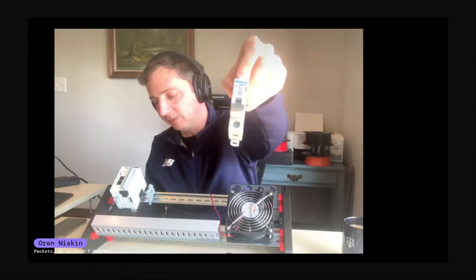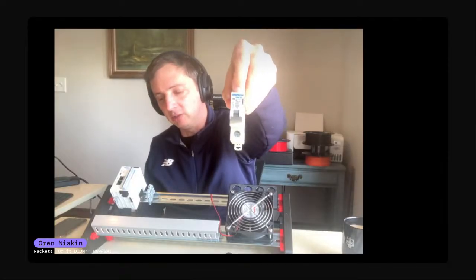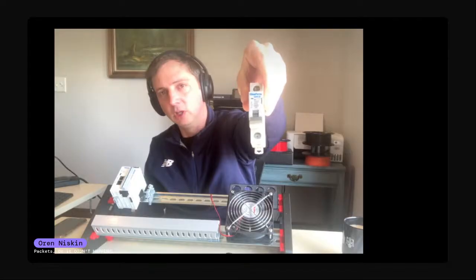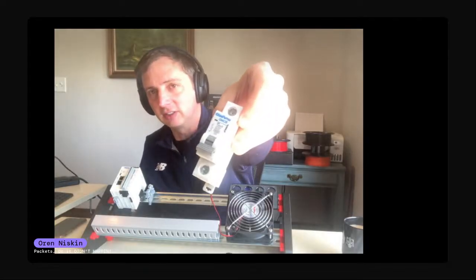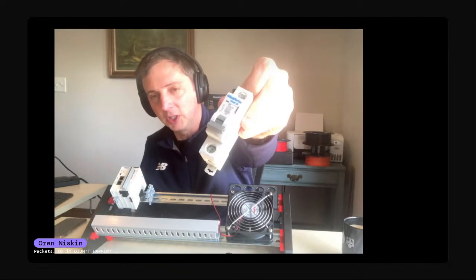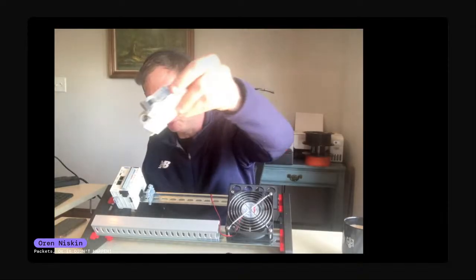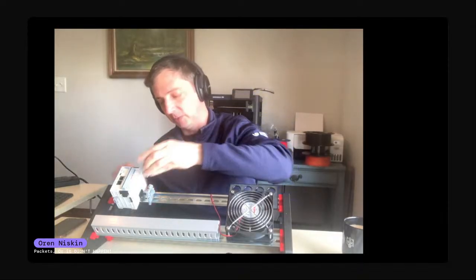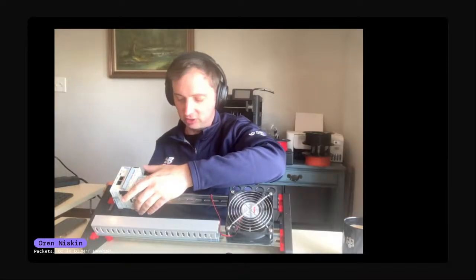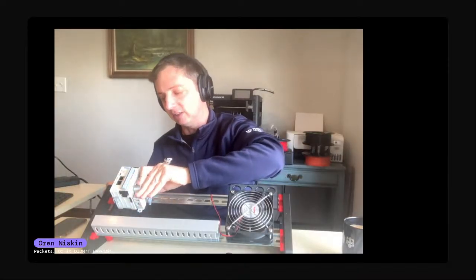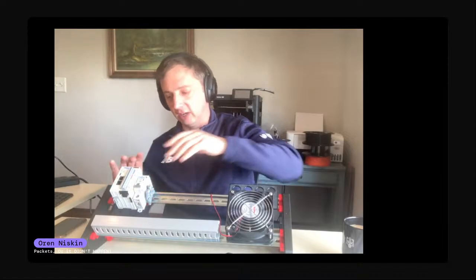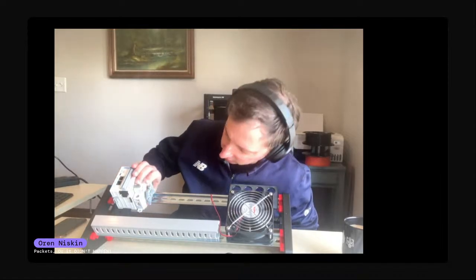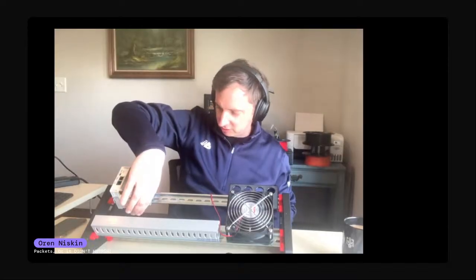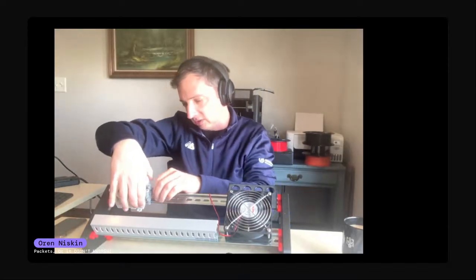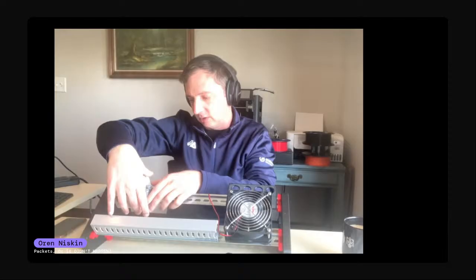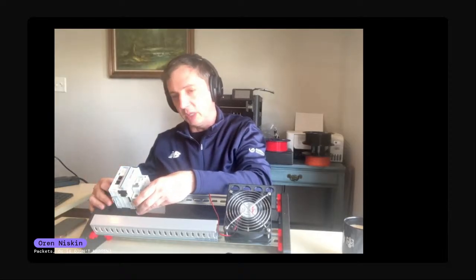In a control cabinet, with wires going out to field devices in an industrial facility, you want them protected in case there's a short or somebody damages a cableway, so they don't cause a fire. That's what these circuit breakers are meant to do. I put the circuit breaker on, set to 5 amps, because that is the current rating of the power supply I got.